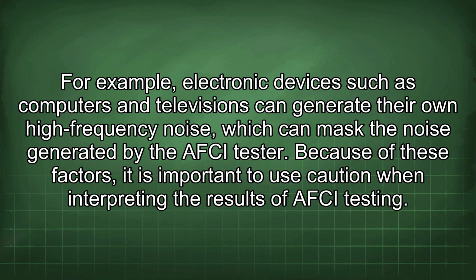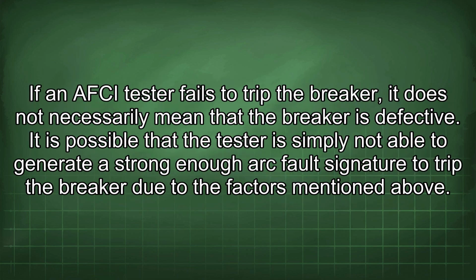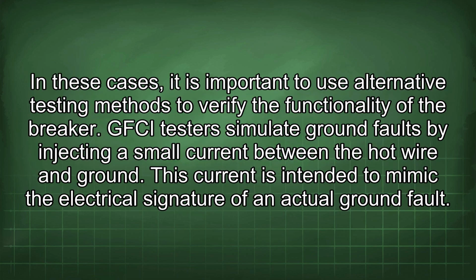Because of these factors, it is important to use caution when interpreting the results of AFCI testing. If an AFCI tester fails to trip the breaker, it does not necessarily mean that the breaker is defective. It is possible that the tester is simply not able to generate a strong enough arc fault signature to trip the breaker due to the factors mentioned above. In these cases, it is important to use alternative testing methods to verify the functionality of the breaker.